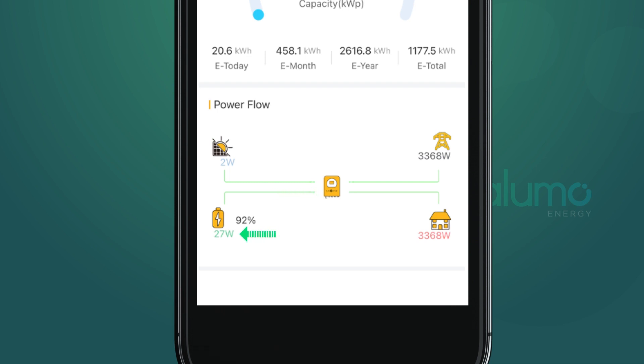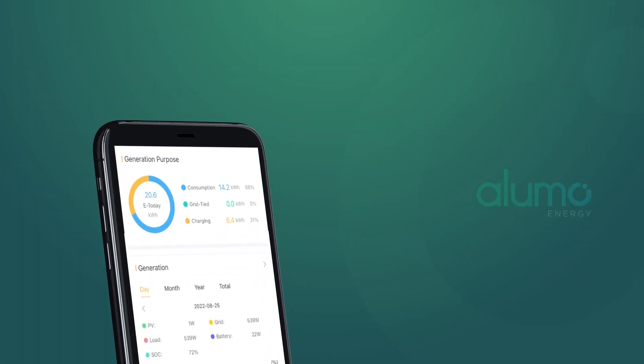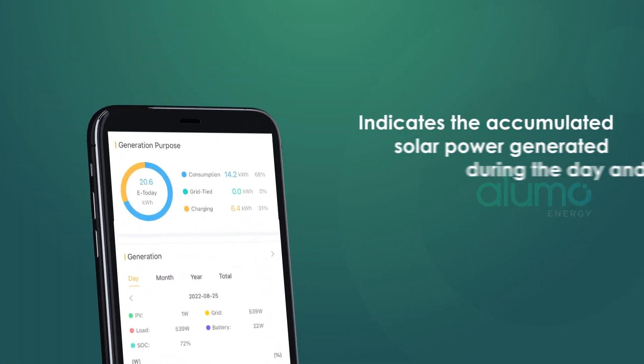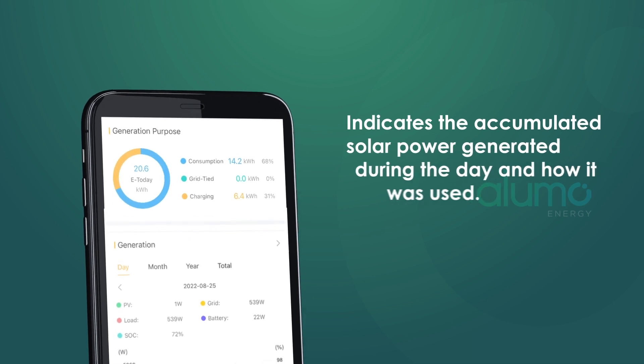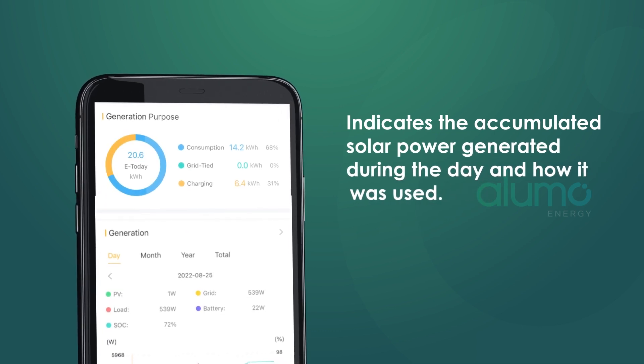When the battery is discharging, the arrow will point towards the inverter icon. The battery state of charge is displayed next to the icon. If the inverter has surplus power available after supplying loads and the zero export setting is unticked, the arrow will point towards the utility icon.